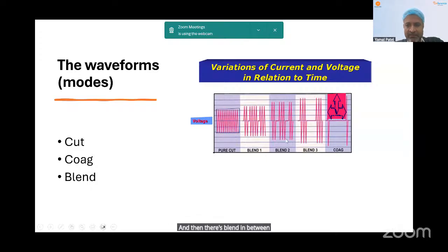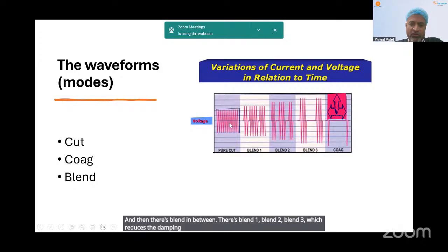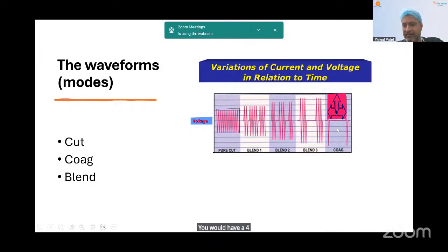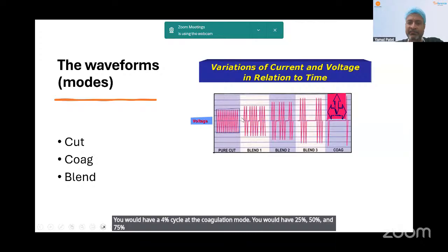And then there is blend in between. There is blend 1, blend 2, blend 3, which reduces the damping. So you would have a 100% cycle, a 4% cycle at the coagulation mode, and 25%, 50%, and 75% cycles, and the voltage increases slowly. So that is what the blend is. It's a mix between the two.